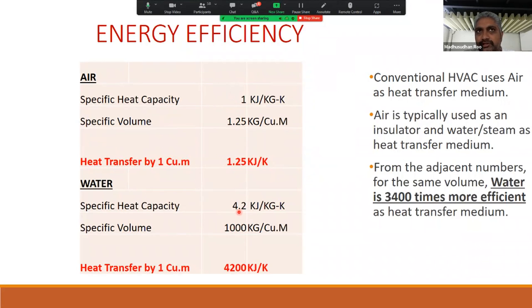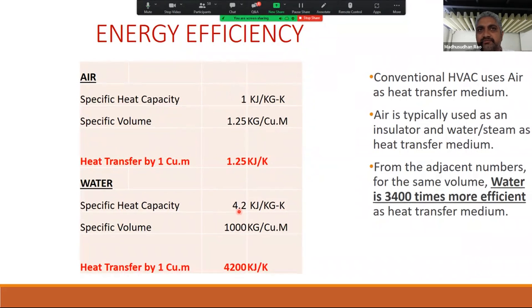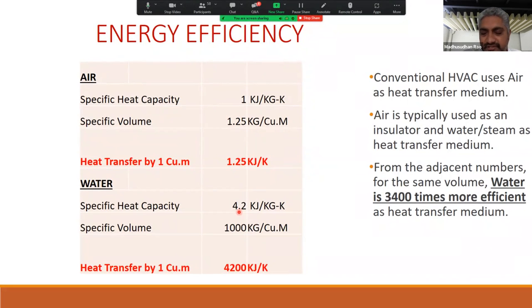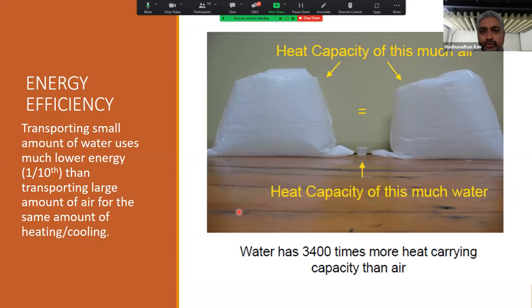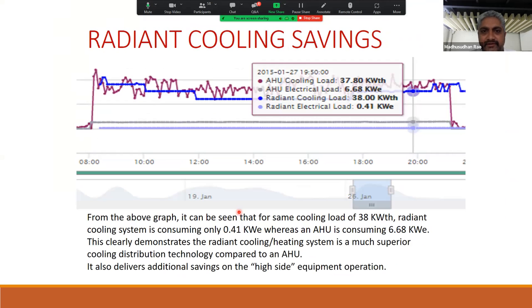And therefore, the energy required to transport the same amount of cooling is much different, because you would need ducts of 2 feet by 4 feet to transport the volume that is required to do a certain amount of heat transfer. Whereas in case of radiant cooling, you only need 16 mm pipes, and therefore the amount of energy that is required would be much lower. And I'll quickly jump to show that.